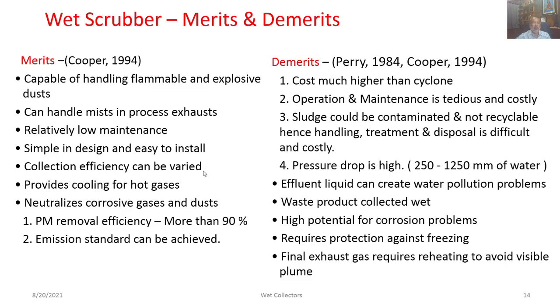I hope you remember about the adjustability of the throat in order to enhance the particulate velocity as well as the gas velocity, and hence the increase in the collisions. It provides cooling for these hot gases. It neutralizes the corrosive gases as well as dust. These wet scrubbers are helpful in deriving efficiency of more than 90%, and hence the emission standards can be easily achieved.